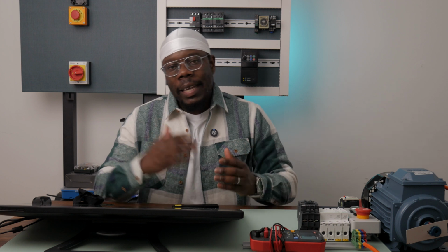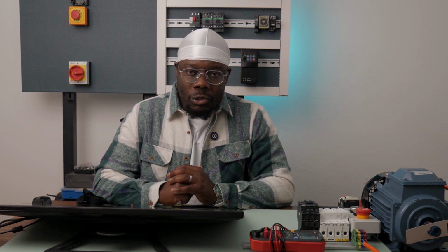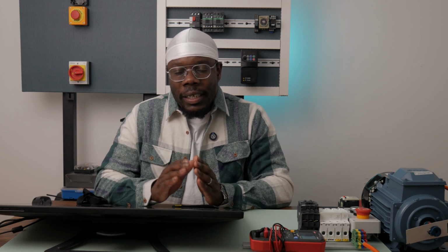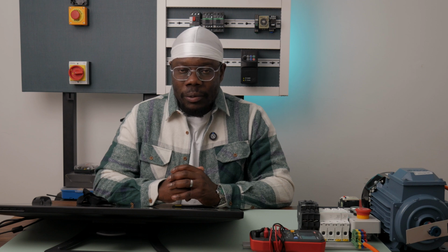By the end of this video, you should be able to understand when to use a direct online starter. The second one, you should be able to understand the advantages and disadvantages of using a direct online starter. Third one, you should be able to draw both the control and power circuit or power schematics of the direct online using IEC 60617 symbols, and you should also be able to wire up both the control and power circuit of the direct online starter and drive a real induction motor with both circuits. You should be able to do all those things by the end of this video.